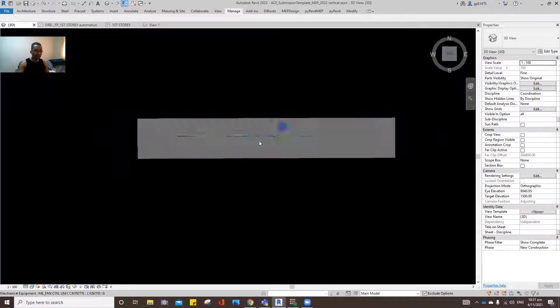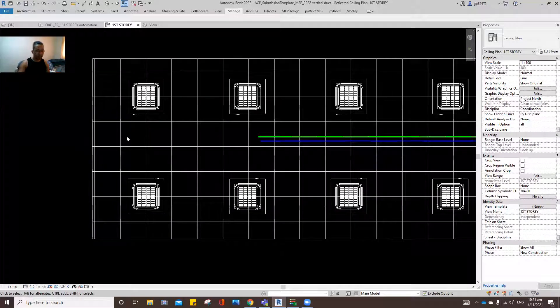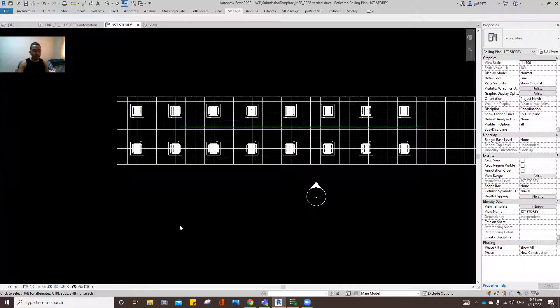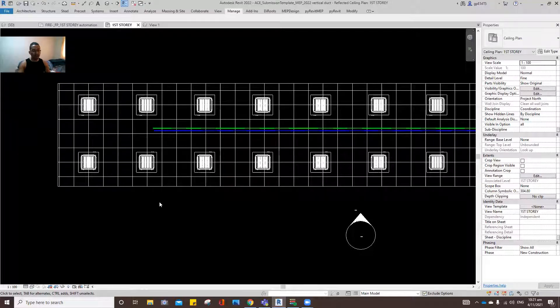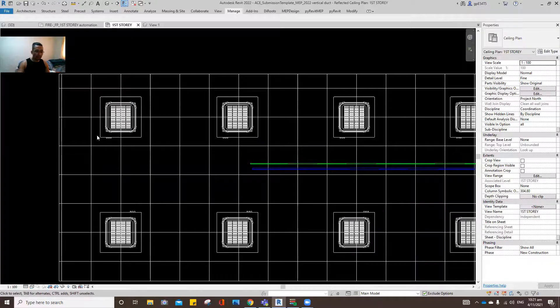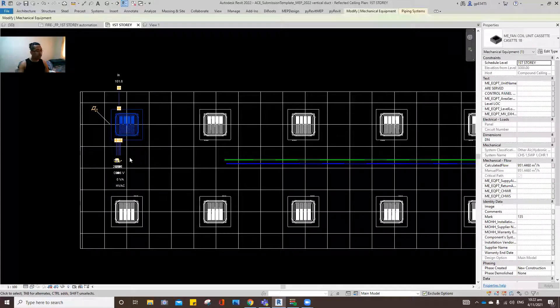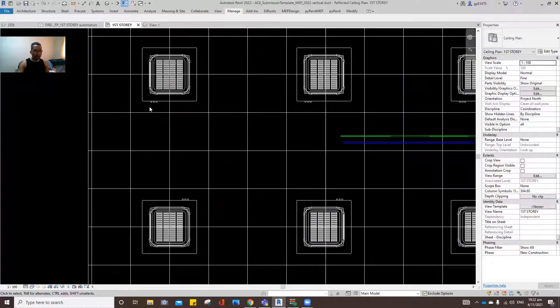In the ceiling, the normal process is to place the FCU first, then coordinate with other disciplines — lighting, speaker, sprinkler — and after coordinating, we have the fixed location of the fan coil unit. That's the best process, especially when working with room data sheets. Once you're coordinated and ready to draw the piping, the starting point of the FCU cassette type is the most important because it will dictate the gradient of the condensate drain.